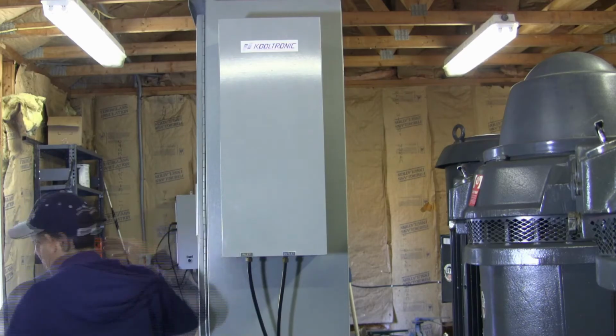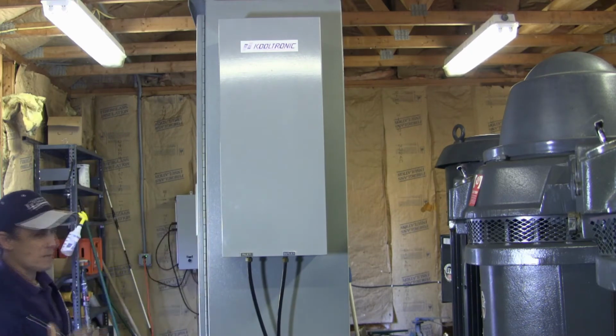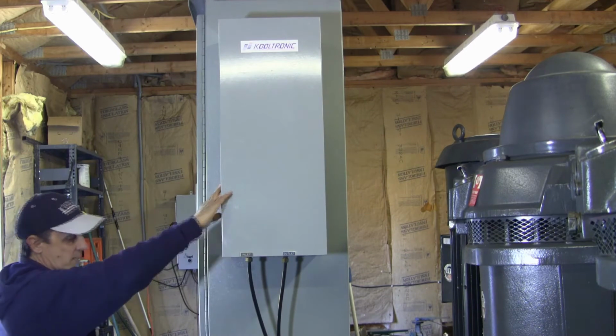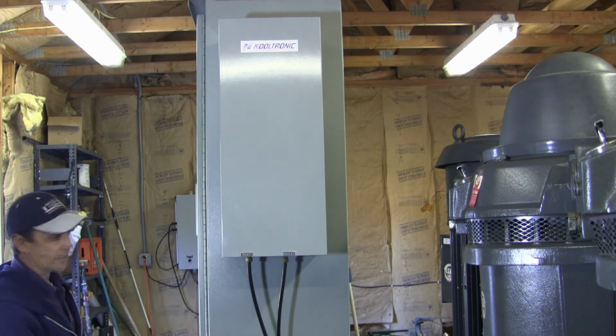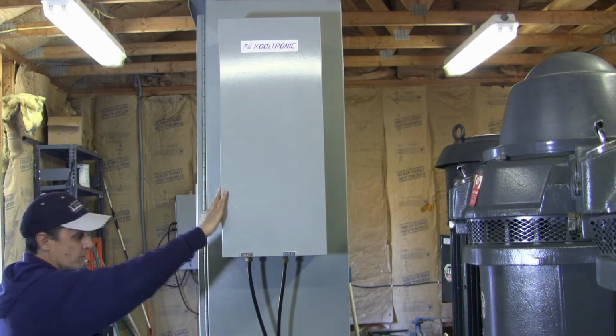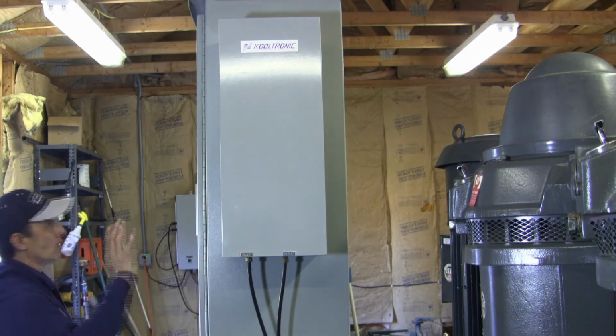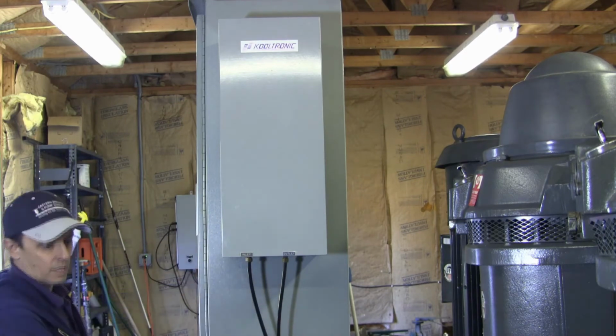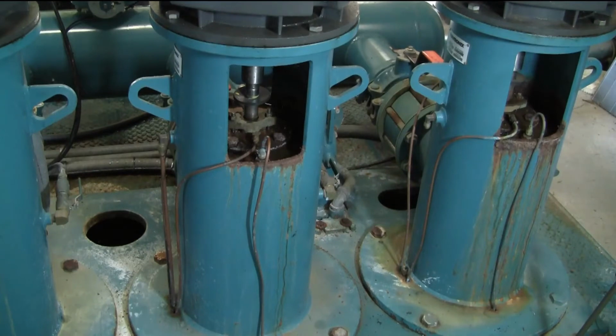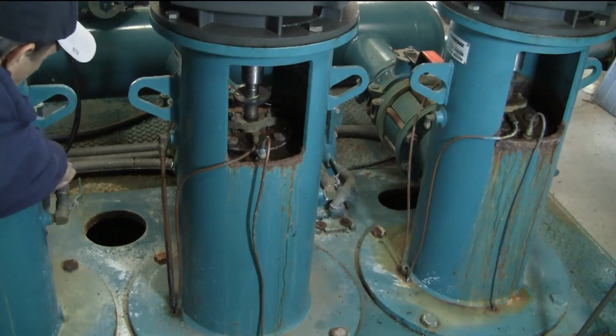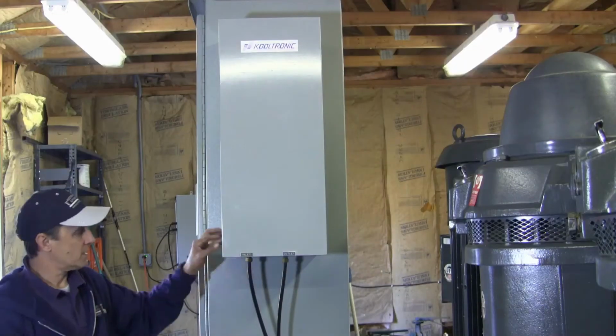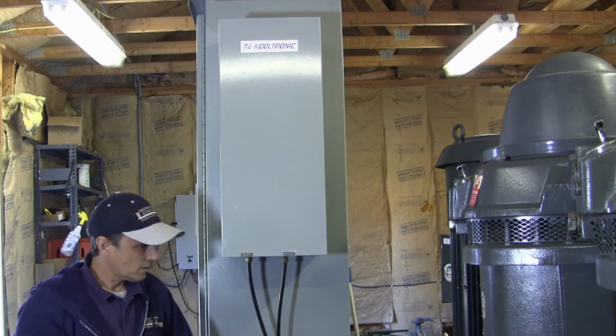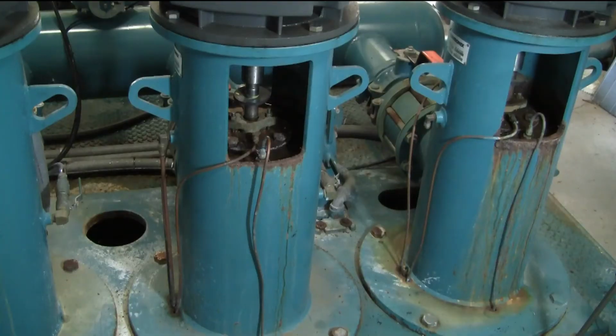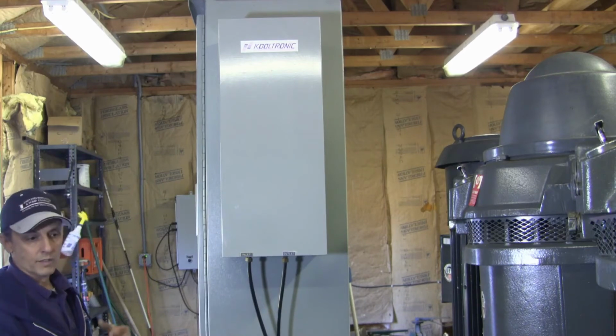The pump panel itself can build up some heat, especially in the summertime. So they install these heat exchangers. Some older stations have air conditioners. A lot of times we use these heat exchangers, and all that's involved is running a tube from... There's a couple different styles. This is what's called a Florida style. A tube runs from each pump head, which would be right here. It goes in the black tube. The tube runs up into the heat exchanger, comes out, and goes over to the relief valve and goes out the relief pipe. That only is running when the pump is running.